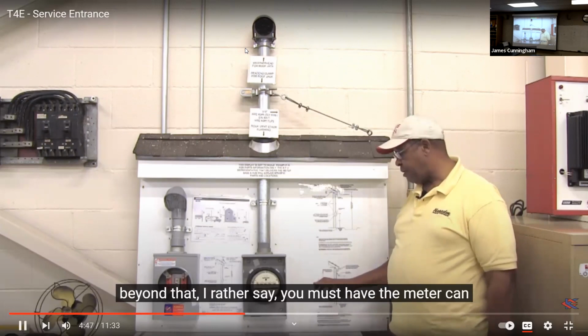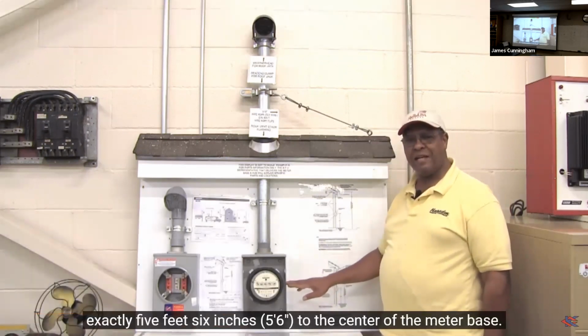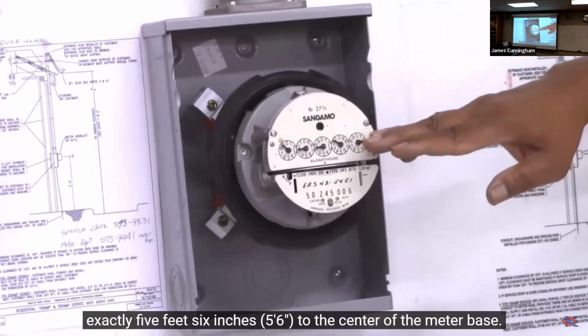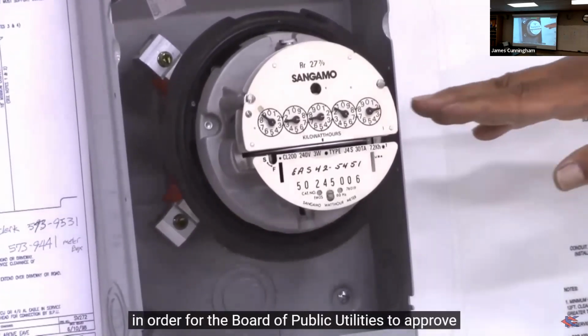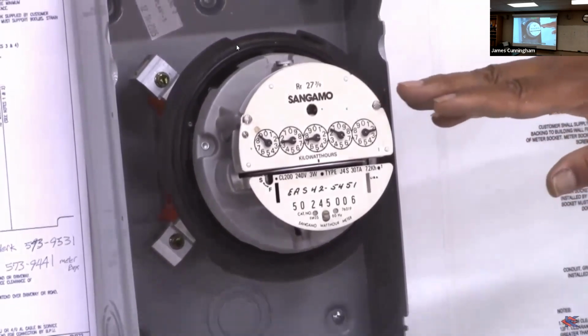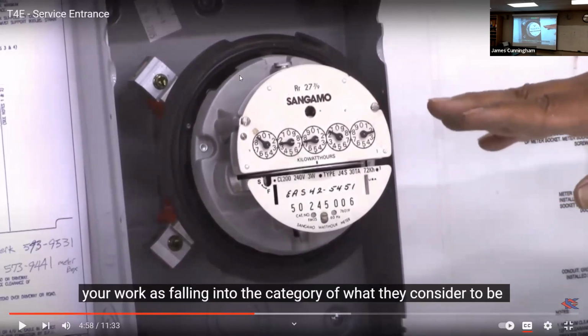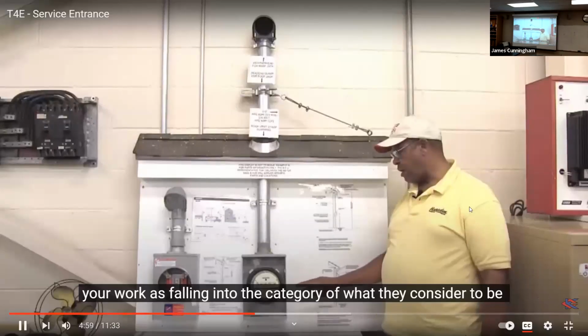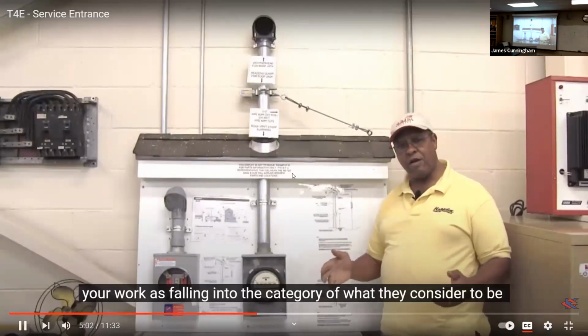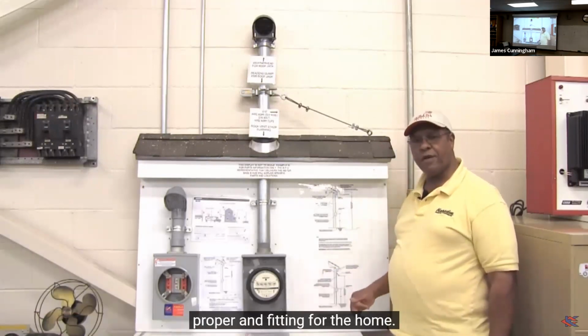Beyond that, you must have the meter can exactly 5 feet, 6 inches to the center of the meter base in order for the Board of Public Utilities to approve it. So their height is 5'6" to the center of the meter base. But the panel's below that. And when we do a meter main, we just set the whole thing at about 5 feet. And so that puts the meter up where he's talking about, puts the breakers in another place. So your work falls into the category of what they consider to be proper and fitting for the home.